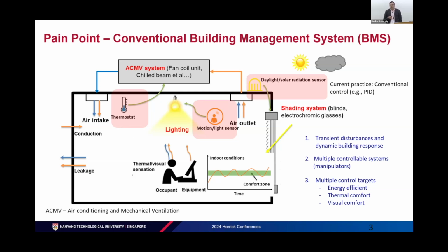When optimizing building energy systems, you need a very coordinated approach across all three systems. For example, what is the optimum level to open your curtains? What are the optimum lighting settings so it's not visually impairing? And when you set your lighting and shading systems in such a way, what is the impact on your ACMV-based systems?